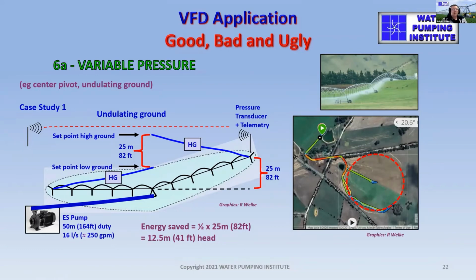Now, we account for that by putting pressure regulated emitters on the center pivot. It doesn't stop there being wasted energy. So what we can do, we can install a portable battery powered pressure transducer with a telemetry system at the end of the center pivot, and we can telemeter that back to the VFD at the pump. So as the center pivot goes around, we can harness that energy waste and slow it down with a VFD. But in so doing, what's the best application for that VFD?